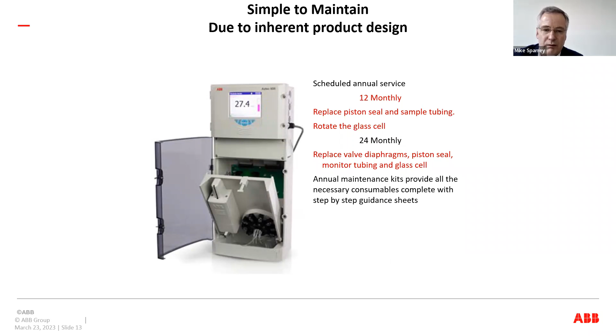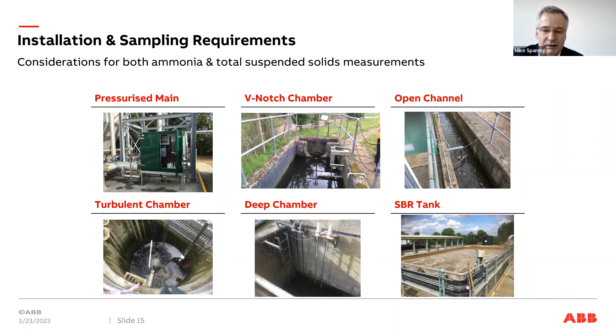But that's the instruments - let's look at the installation and sampling requirements, because depending whether you're on the clean water side or the wastewater side, there are different challenges. Looking at typical applications we've seen: a pressurized main, a V-notch weir, sedimentation, an open channel like a river intake or final effluent type take, and then the classic turbulent chamber or deep chambers and sequential batch reactors.